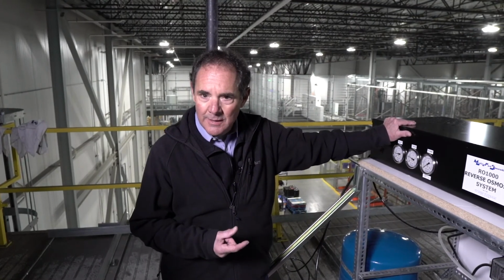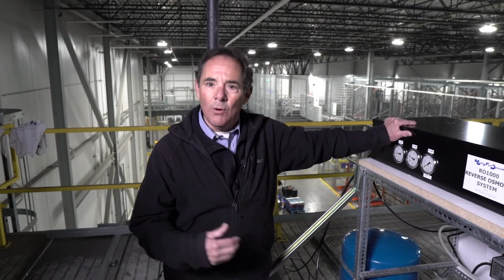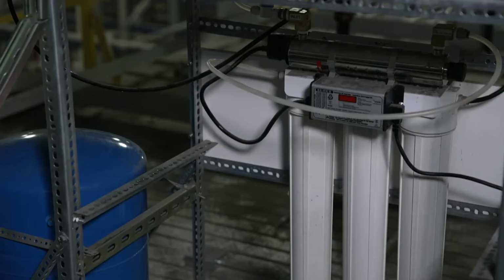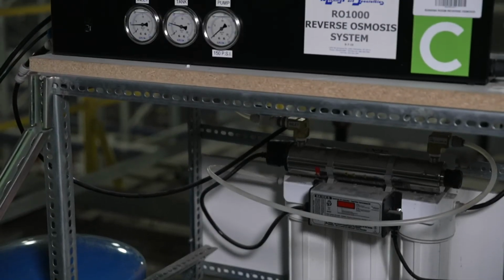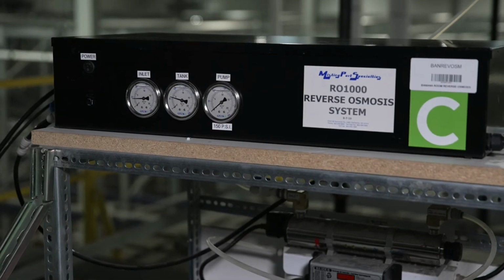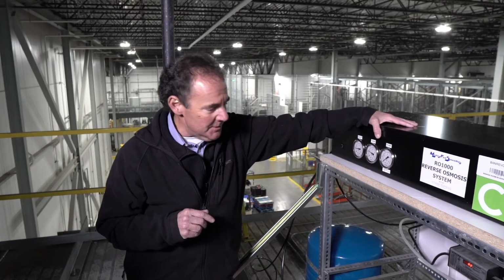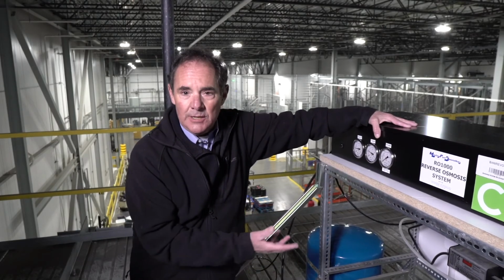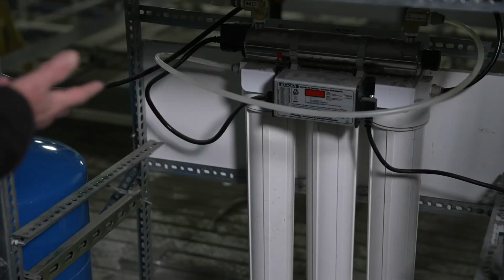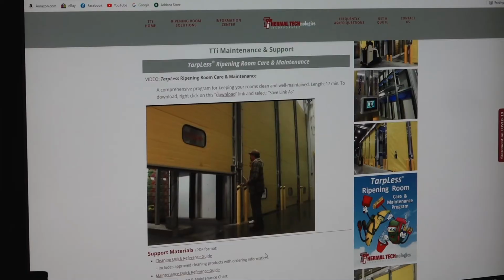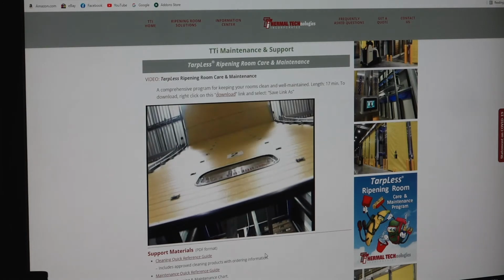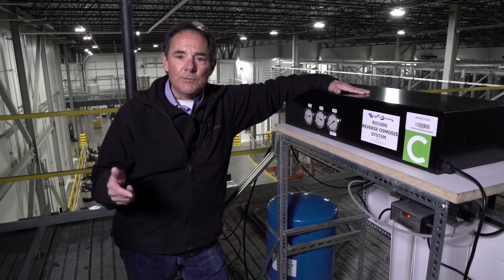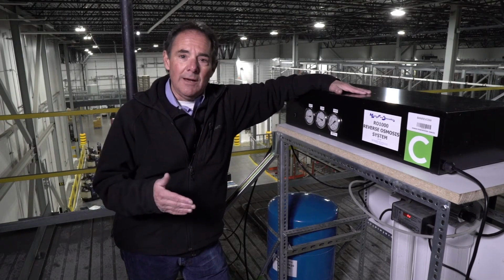This is the reverse osmosis system, also known as the RO system. It's either located on the top of the room or next to the room on the main level. The reverse osmosis system delivers clean, filtered water to each humidifier in every room. It's important to know that the RO system contains filters that need to be changed on a regular basis. Be sure to watch the Tarpless care and maintenance video located on the Thermaltech website to get the best results from your ripening rooms at all times.